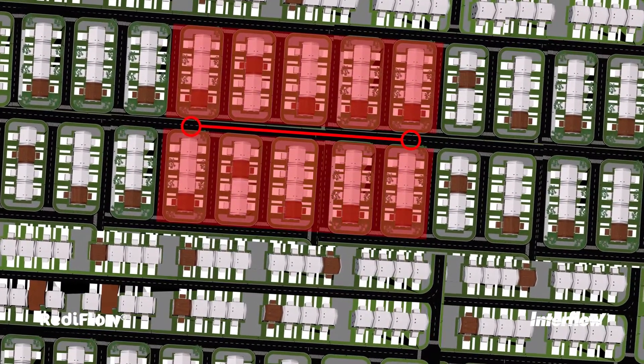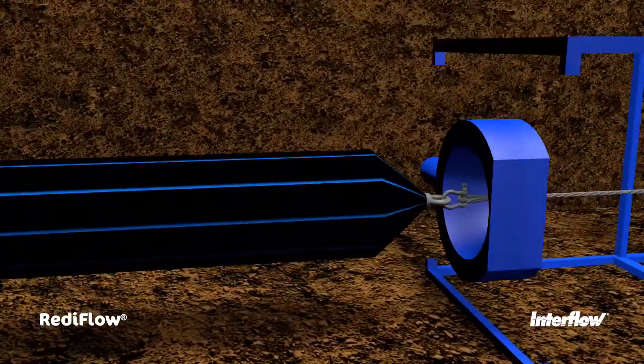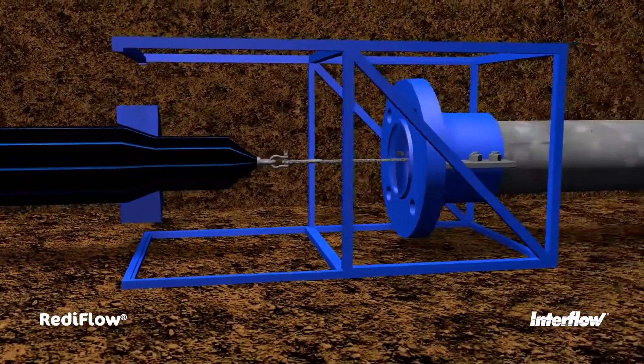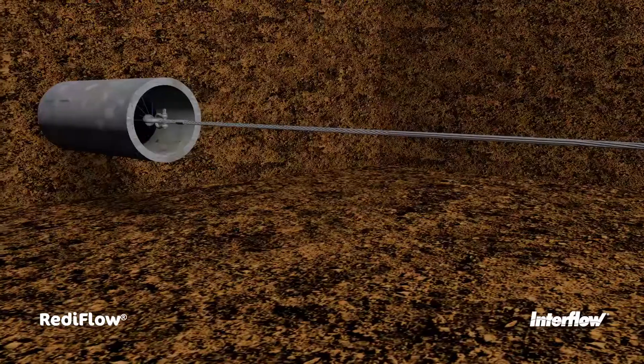With the pipeline isolated, lining works can begin. The RediFlow pipe is towed under tension through a static die, reducing its diameter and allowing it to pass through the host pipe.